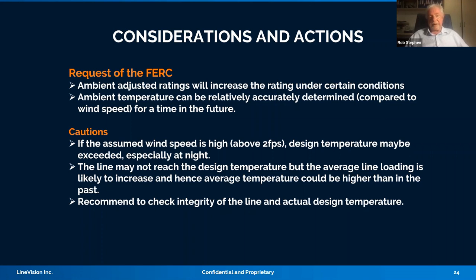If the assumed wind speed is high, design temperature may be exceeded, especially at night where your wind speed drops. So you need to just be aware of that. Your line may not reach a design temperature, but remember, if you're removing constraints, you're most probably going to be increasing the average loading on a particular line. So if you're looking at constrained lines and doing any form of uprating, especially this kind of thermal uprating where you're looking at rating uprating and not really changing conductors or anything like that, it would be a really good idea to do a thorough investigation of the integrity of the line.